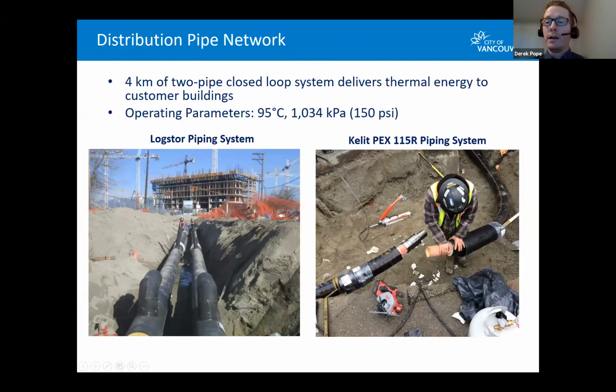This is what our distribution network looks like, and it's just buried pipe. These pipes actually come from Denmark; we've adopted the European piping system. It's insulated steel piping that runs through our roadways and connects into each of the buildings that we service. The piping is capable of accommodating our operating pressures and temperatures of 95 degrees Celsius and 1,000 kilopascals.